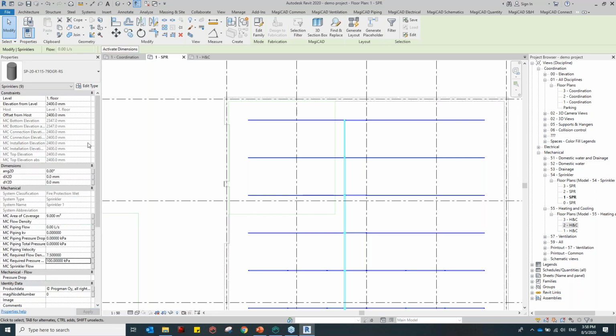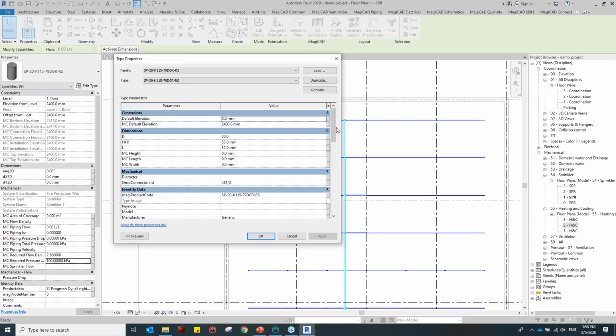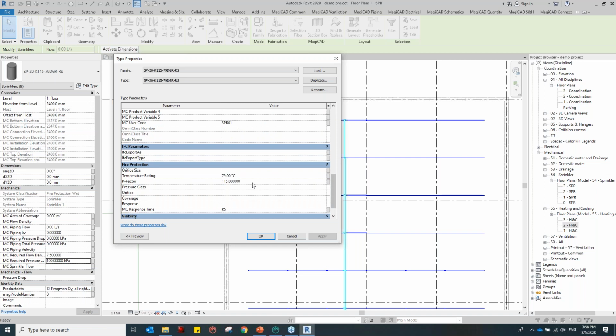And other than this, what else information do you need to consider to do the sprinkler calculation? When you look at the sprinkler technical information, you also need to specify the sprinkler K factor, which is coming from the MagiCAD. Later I will show you MagiCreate, where you can put all this technical information into the products. If it is manufactured, by default it comes from the manufacturer. If it is a generic product, the user can modify this information and use that in the calculation. Other than that, you also need a temperature rating. So make sure you put these two pieces of information in the model. If you want to modify, you can modify here.